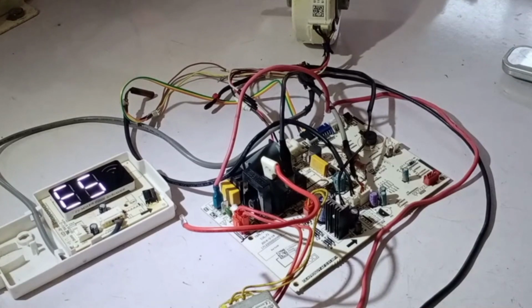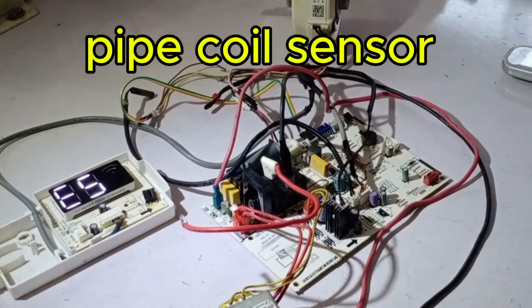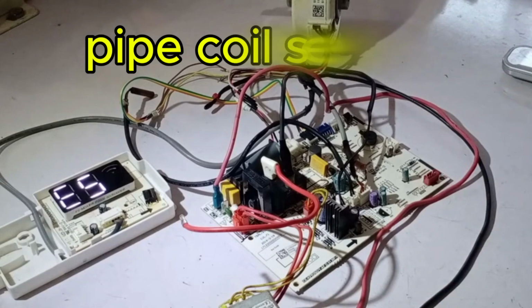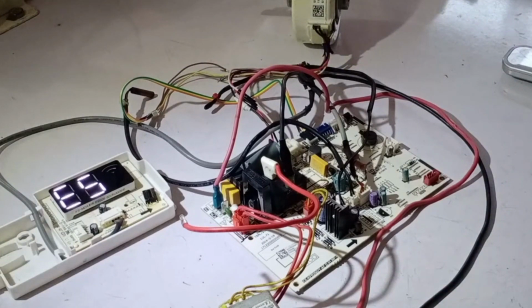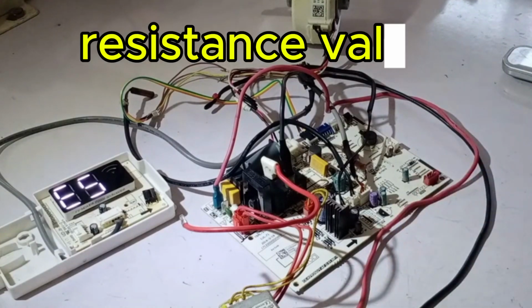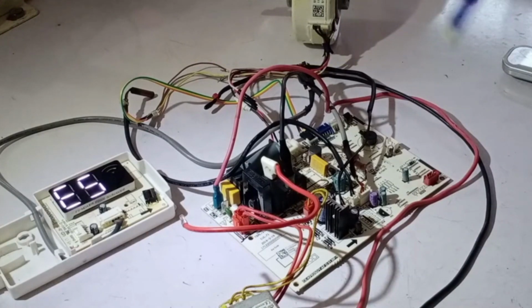Whenever an E5 error appears, it indicates that the pipe coil sensor has become faulty, has short-circuited, or has gone open circuit. To resolve this, you should check the pipe coil sensor and verify its condition. It is also important to know the exact resistance value of this sensor so that you can replace it with a sensor of the same resistance. Once you install the correct replacement sensor, the E5 error will disappear from the display. Now, I will show you where this sensor is located on the PCB.